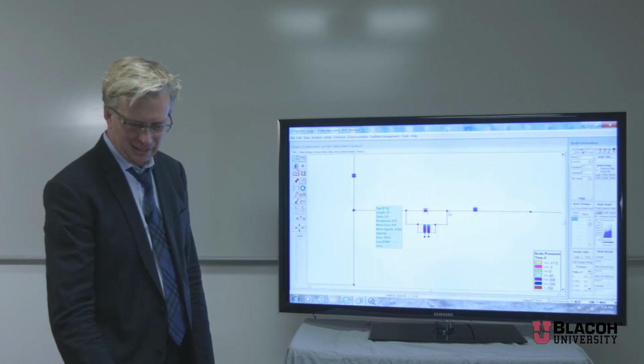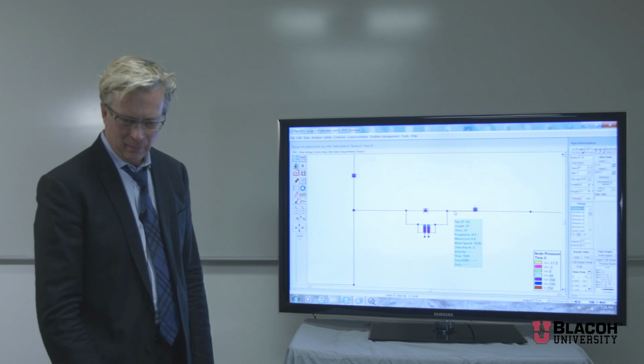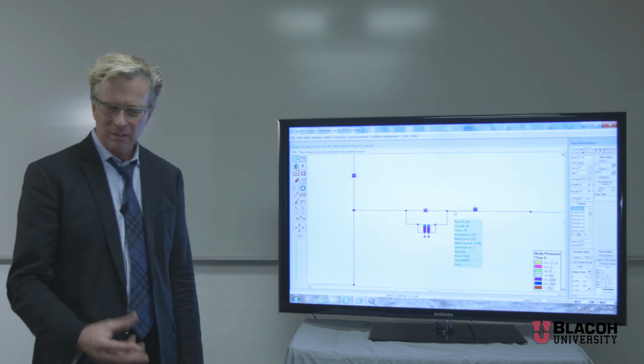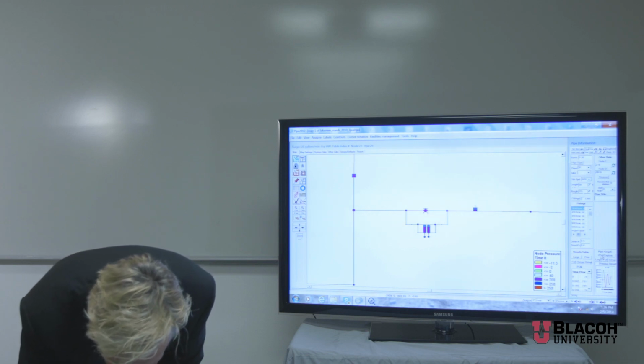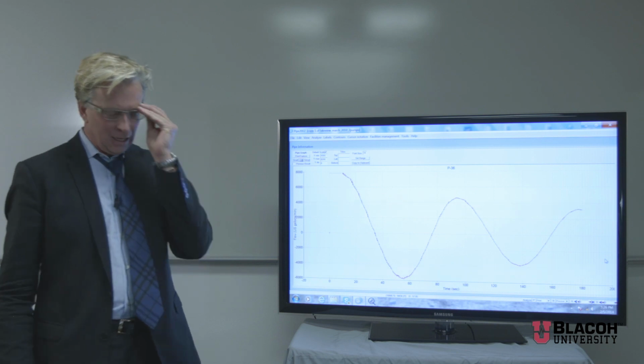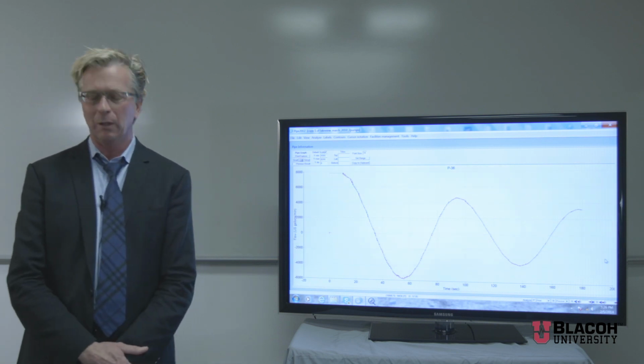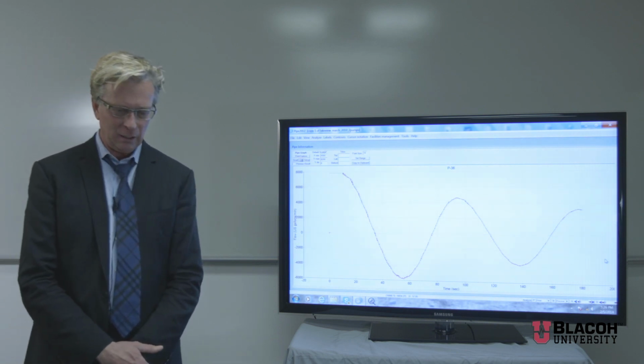Just a little bit more data. It's just going and comparing the flow meter data to what was happening in reality. Here's what our flow rate did. We were pumping almost 8,000 gallons per minute with 2 pumps. And you can see how it dropped off.